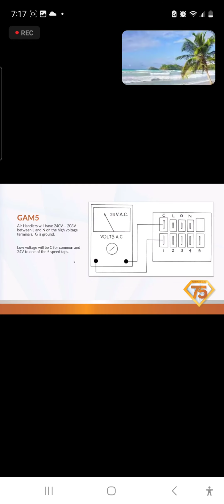On a GAM5, the wiring's a little bit different. Like I said, we're not coming off a board with a GAM5. The wires will go straight from each of your controls. So like the G wire for constant fan comes in on the green wire, and it goes straight to the motor. And where your green wire lands on tap 1, 2, 3, 4, or 5 would be your constant fan. Here we're still going to have the high voltage marked line and neutral, L and N, although it's 240 volts now. And so you're going to have 120 volts going to each of those legs.